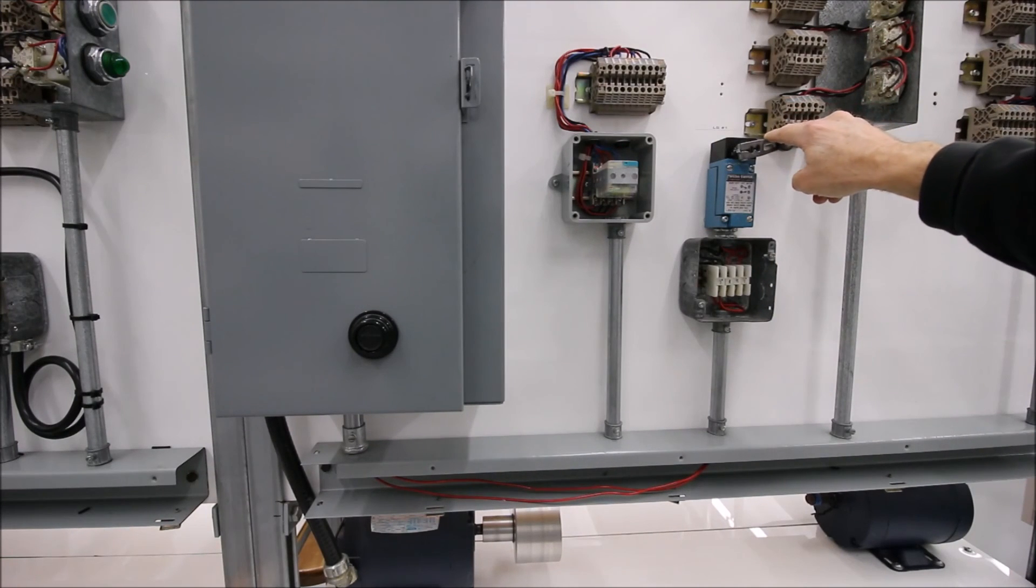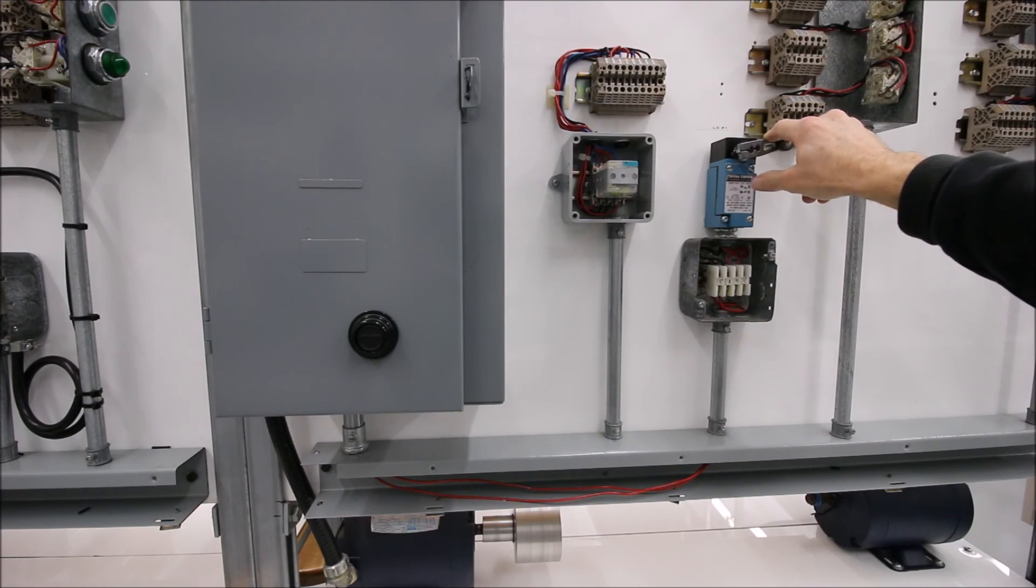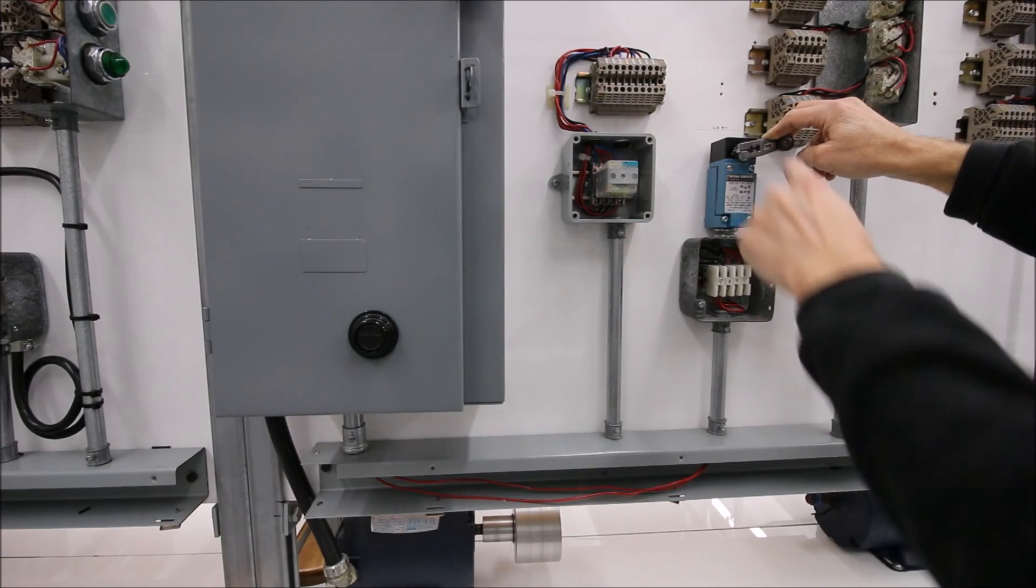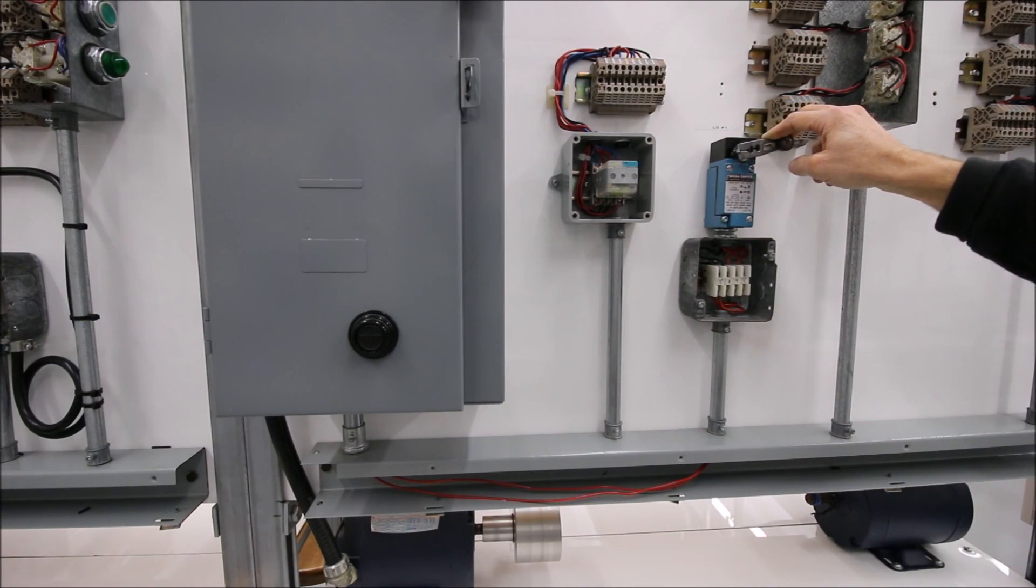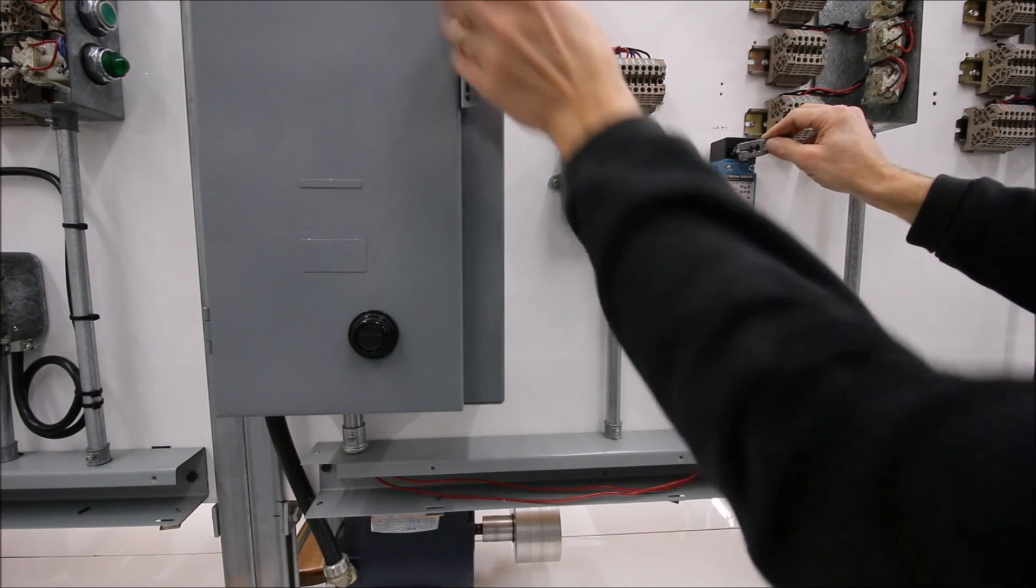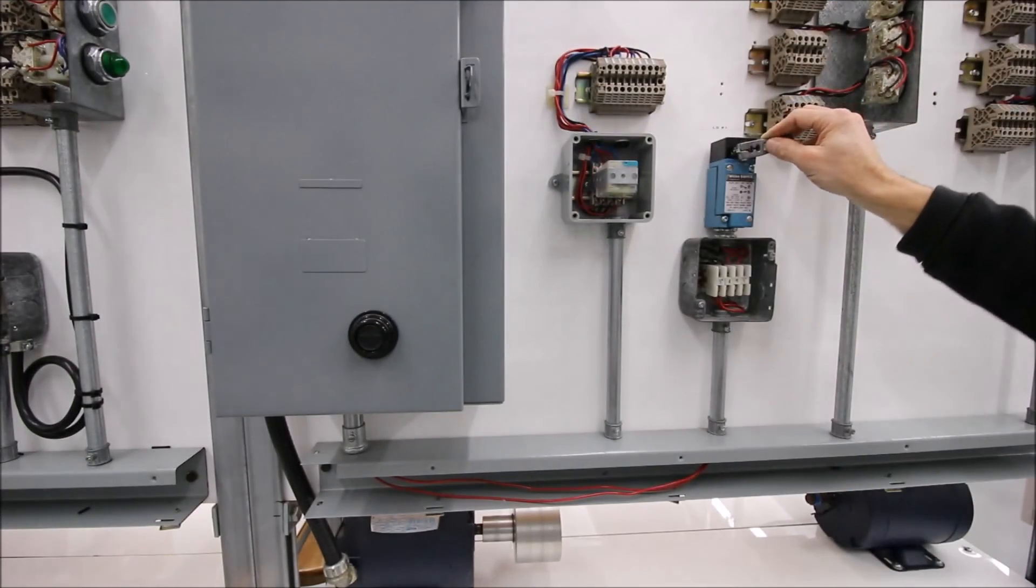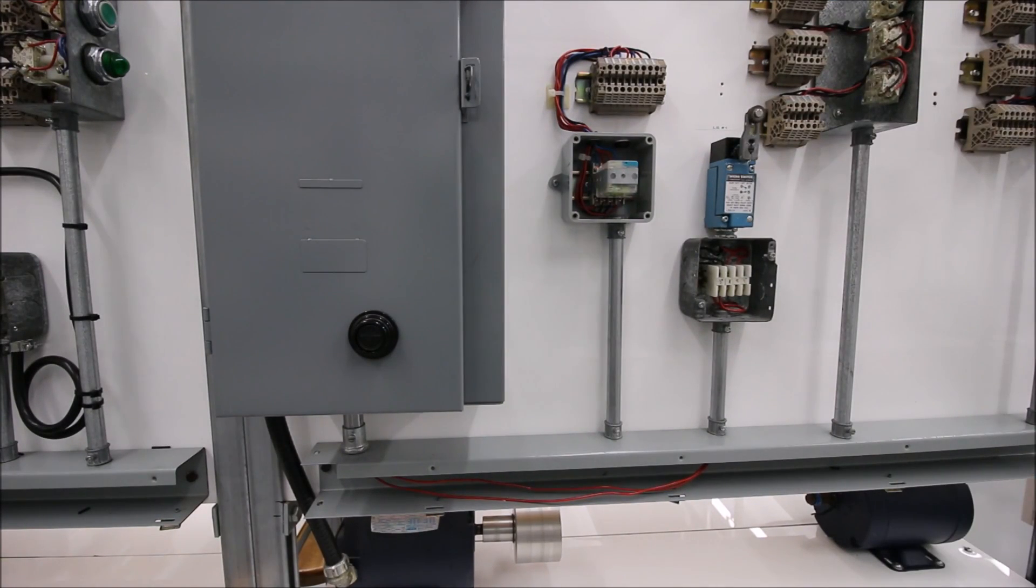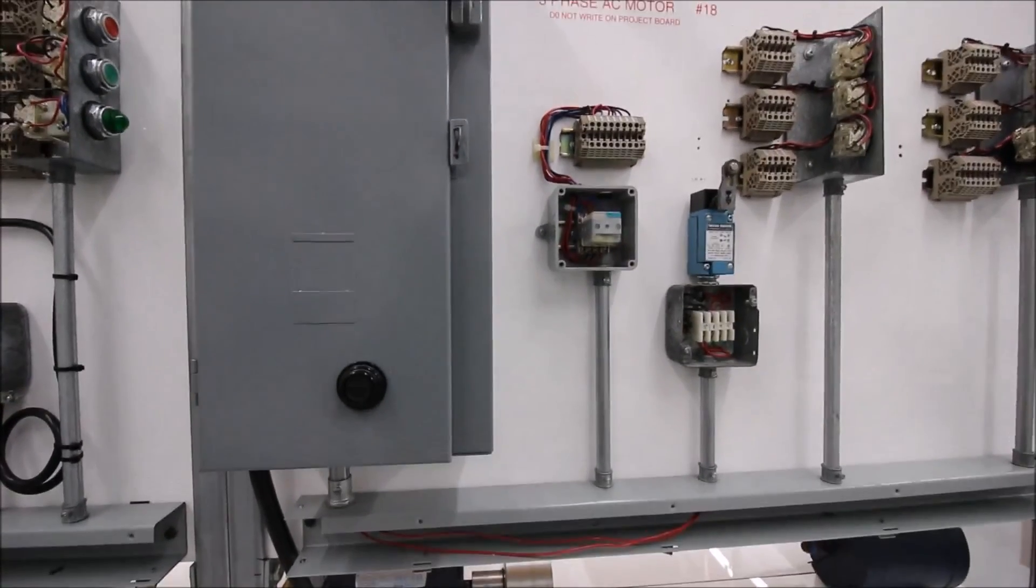As long as that limit switch, or more likely a thermostat or pressure contact, is calling for that pump or that fan to turn back on, it's low voltage release. Then if you have a brownout, the motor turns off. As long as this is still calling for the motor to turn back on, when the power is restored, then the motor goes right back on. Alright guys, hopefully that covers everything for the two-wire. Next video is going to be on the three-wire.